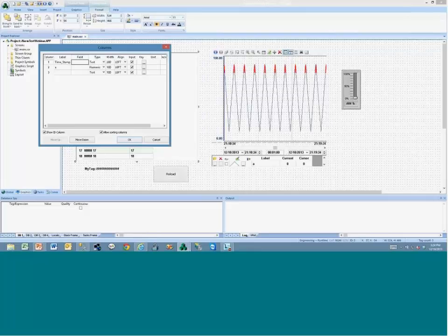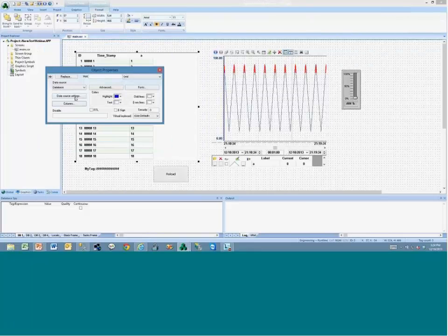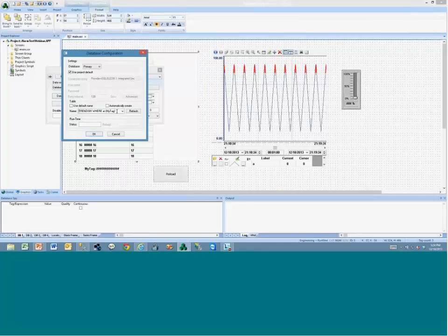Both in the field here, as well as in the table field, you can have string tags between curly braces, and during the runtime, you can change the values of those string tags and toggle the reload tag to execute whatever queries you want to do on the SQL Server database. From the security point of view, you have to be careful about how you expose this to the user to avoid injections. But when you are designing the system, you have the ability to do that.